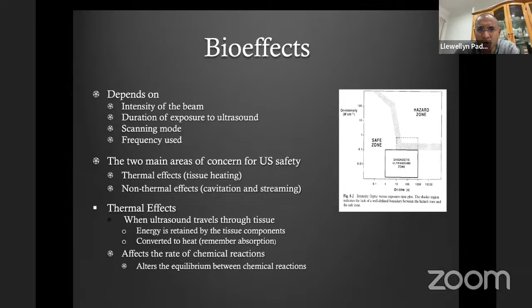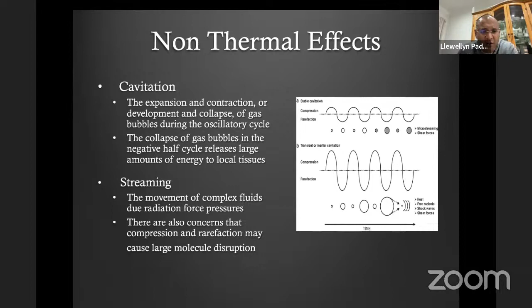The non-thermal effects are things like cavitation and streaming, and these relate to the expansion, contraction, development and collapse of bubbles during the oscillatory cycle. The collapse of gas bubbles in the negative half of the cycle also releases some energy into the local tissue. Streaming relates to the movement of complex fluids due to radiation force pressures, and these are also something that we've got to bear in mind.